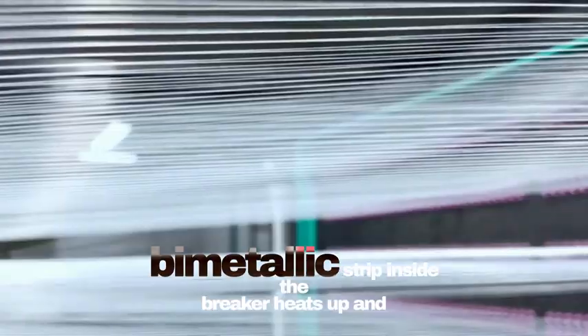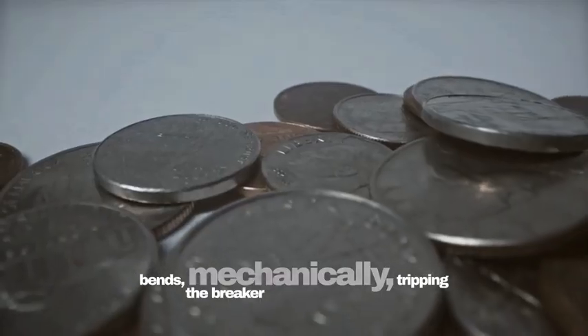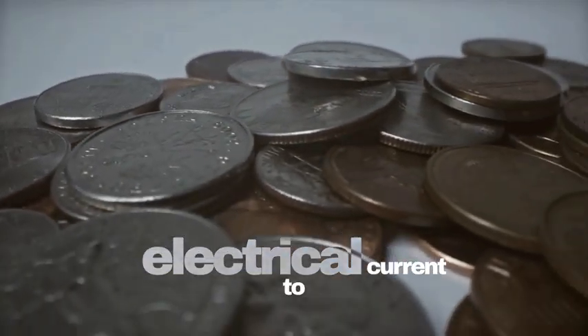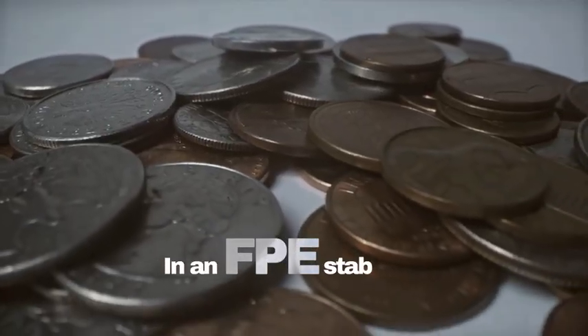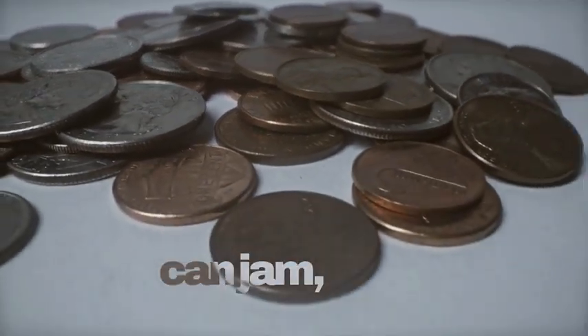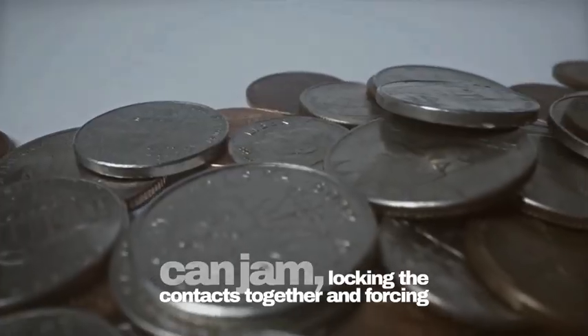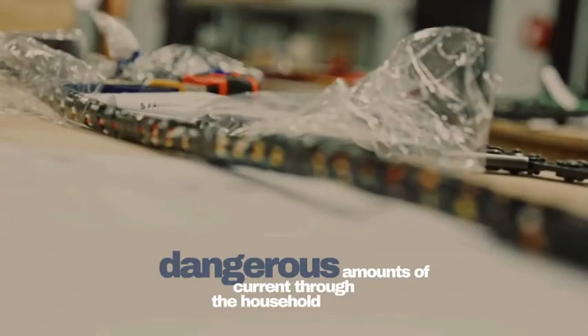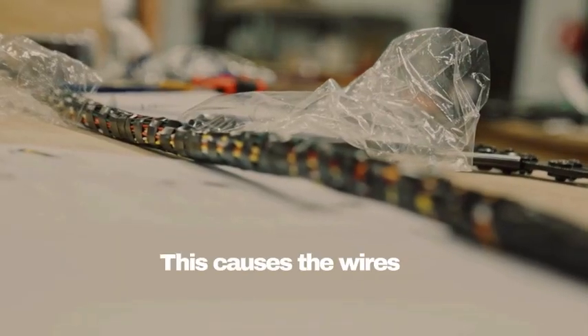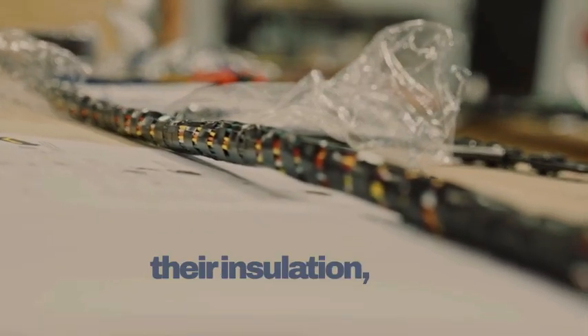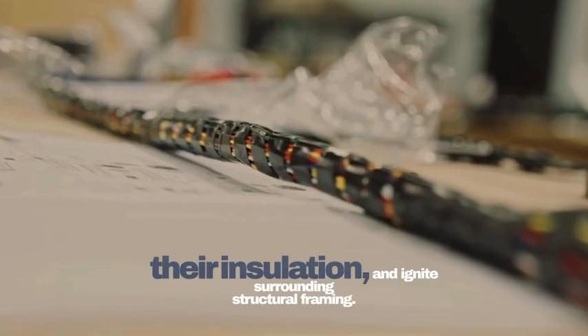In a standard electrical panel, when current exceeds the safe ampacity rating of the wire, a bimetallic strip inside the breaker heats up and bends, mechanically tripping the breaker and interrupting the electrical current to prevent a fire. In an FPE stab lock panel, the breakers can jam, locking the contacts together and forcing dangerous amounts of current through the household wiring. This causes the wires to overheat, melt their insulation, and ignite surrounding structural framing.